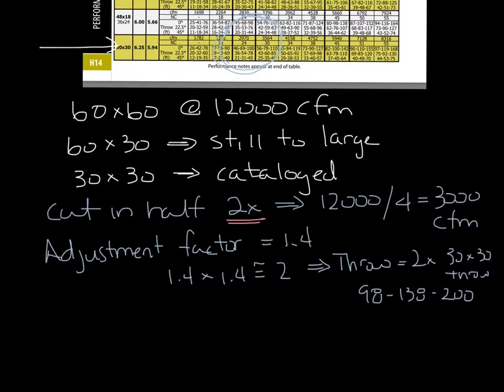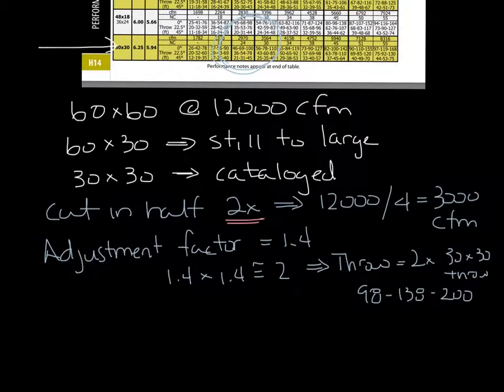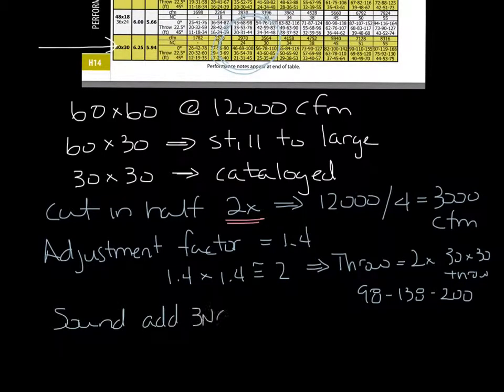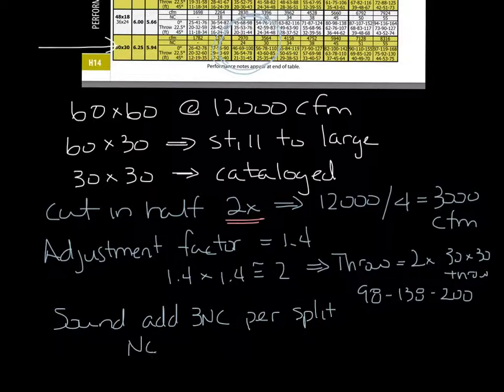For the sound of the oversized grill, it's a good rule of thumb to add 3 NC for each time you split the grill. NC-24 is the cataloged 30 by 30 sound data, so add 3 twice and you get NC-30.